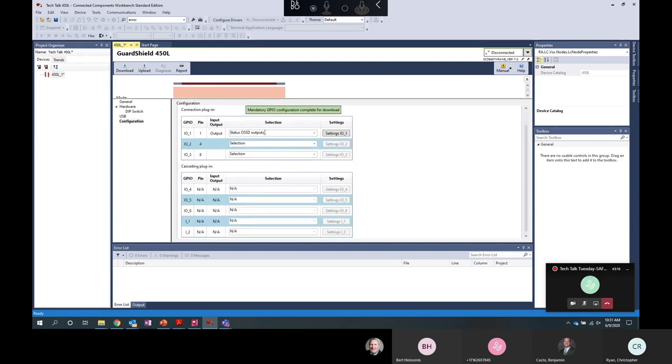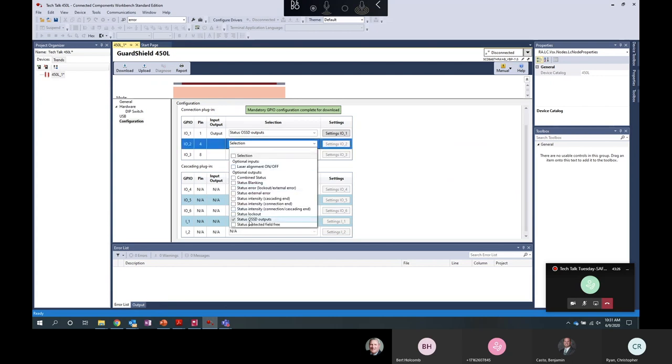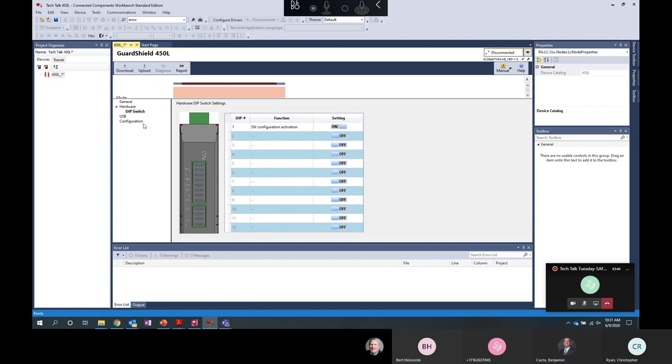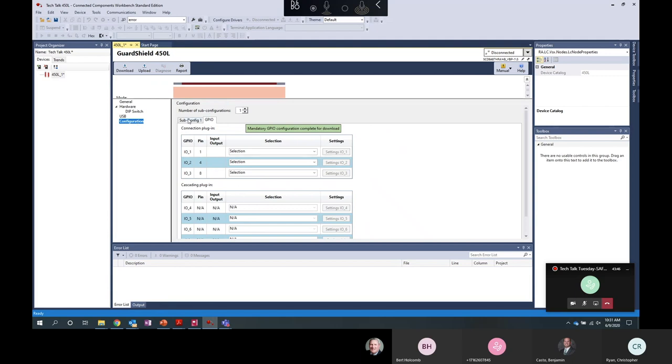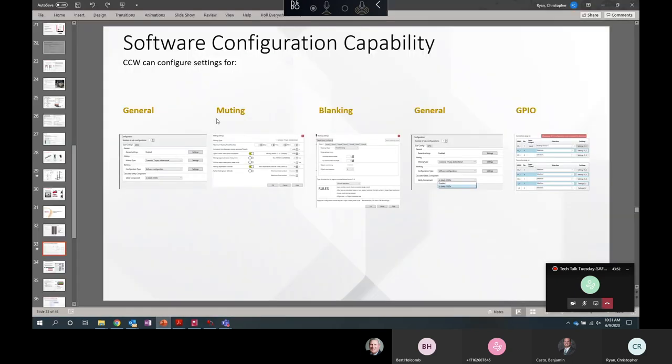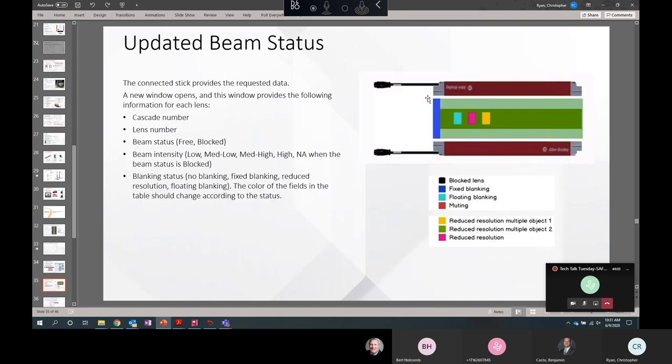So your GPIO, I actually have mine set up. I have one of my auxiliary outputs set to just give me the status of my safety outputs. So I have a light that's on when my safety outputs are on, but this shows you all the options. So you can wire these status signals to your PLC or your status indicators or alarms or lights. You can see the status of your DIP switches. If I turn this off, then you can see what configuring with DIP switches allows you to do. So if I turn software configuration with DIP switch 1 on, then I just do it from here. And I go to subconfig and I can enable muting or blanking and do all my configuration there. So updated mode statuses. When you change your configuration, it'll be unlocked. You have to confirm your lock status. We have error, lockout modes, beam statuses. And you'll see this. If you have fixed blanking on the first half, you'll see it all blue. And then beam status is here. Whereas before you could just see if it was blocked or not.